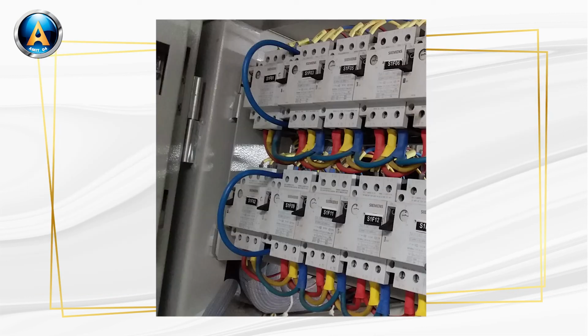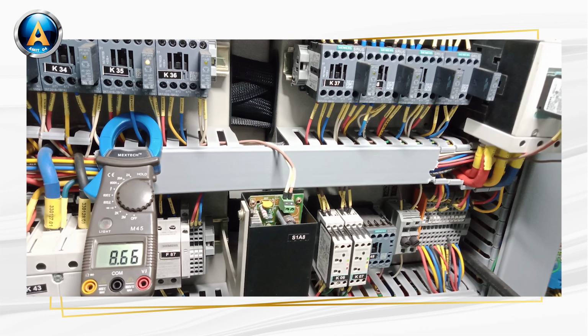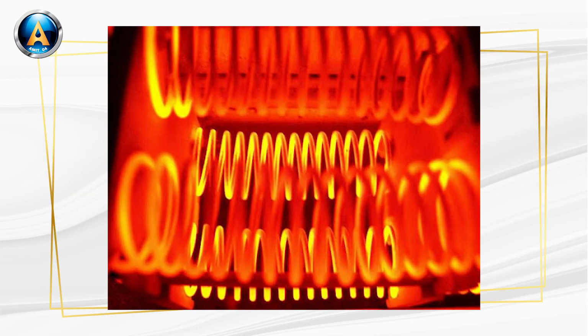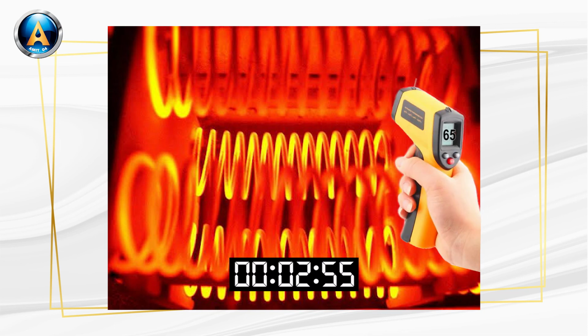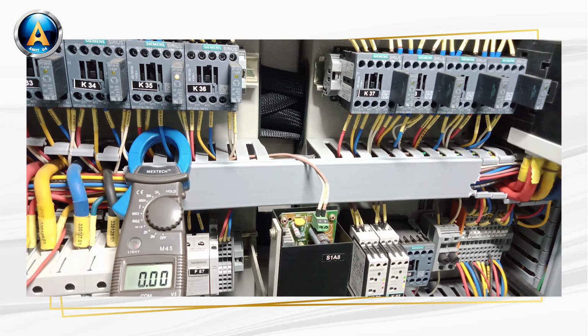So in this situation, both heaters become active manually without the blower. So the air temperature near the heating coil may reach 65 degrees centigrade within a maximum of 3 minutes after starting the heater unit, and simultaneously the K35 and K40 contactors should open by the OHP device. If it happens, then it is confirmed that the OHP device is working properly.